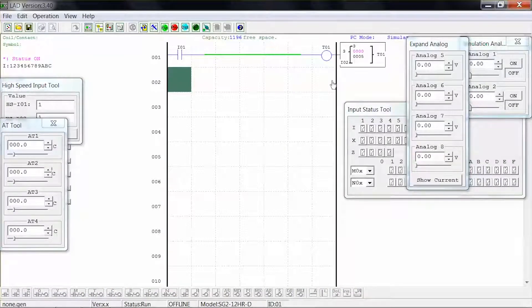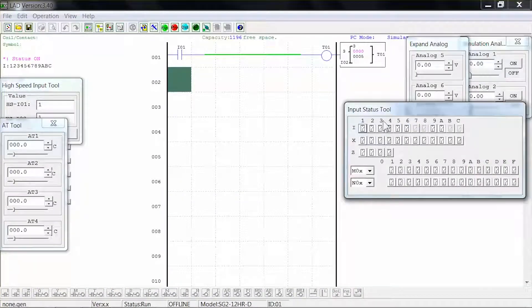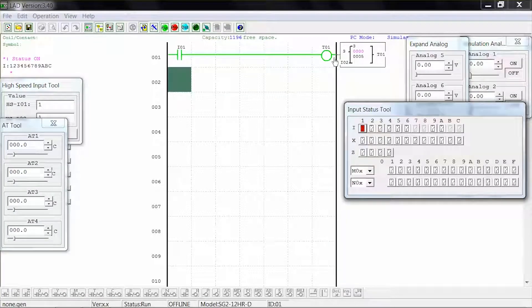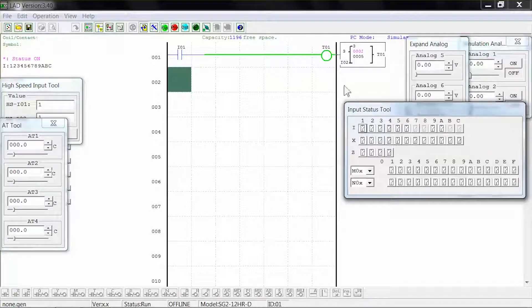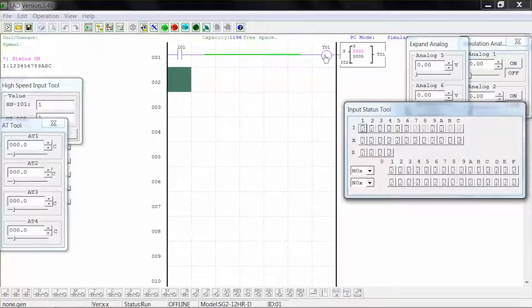On the input status tool window, close input 1. Note that the coil activates, but the timer does not start counting. When you open input 1, the coil remains activated but the timer begins to count, and upon reaching 5 seconds the coil deactivates.